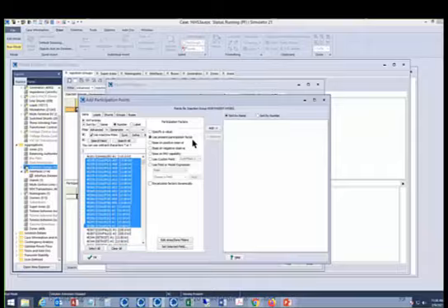Then the next thing you have to do is initialize the participation factors. So these options, depending on whether you have a generator or a load or a shunt, you might see some different choices here. But if we wanted them all to have the same value, then we could pick that. We could maybe set them all to 1. And what that would mean is that if it's participating in a transfer, every generator would incrementally move by the exact same amount, no matter how big the generator is or things like that.